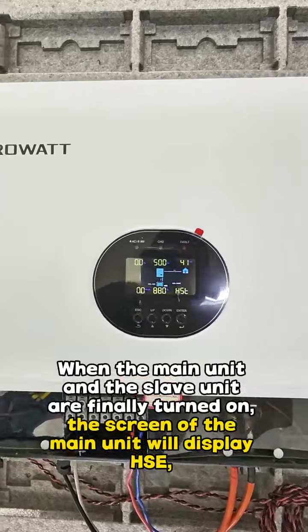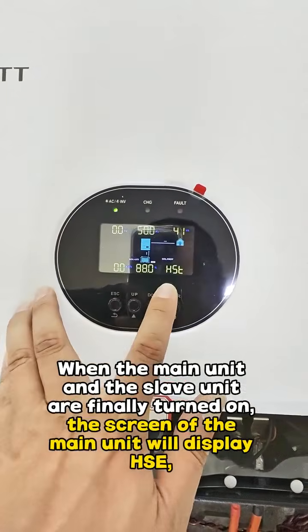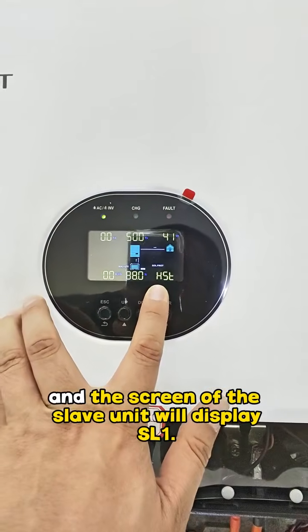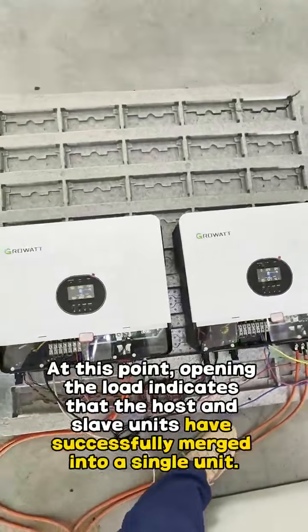When the main unit and the slave unit are finally turned on, the screen of the main unit will display HSE, and the screen of the slave unit will display SL1. At this point, opening the load indicates that the host and slave units have successfully merged into a single unit.